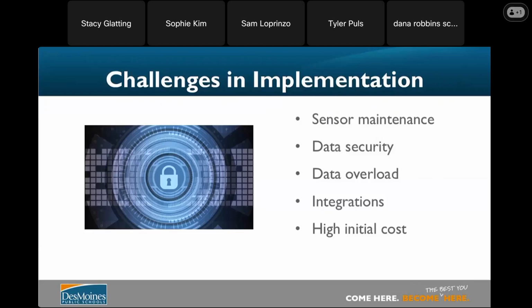Some challenges. It's definitely not all easy. Data is only as good as the sensors that provide it. So if CO2 sensors go out of calibration, CO2 sensors become unreliable, temperature sensors become unreliable. So calibrating those and replacing as necessary are definitely keys to maintaining an adequate system.